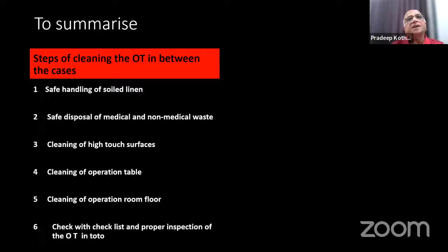The next talk was on instrument reprocessing. Cleaning, as I told you, is the most important step. It should be done as early as possible after the surgery to remove the debris as well as the blood clots. Second is inspection of the instruments for proper functioning, whether there is any debris remaining or not. If they are not functioning properly, you can lubricate them. If they are stiff, either they are not cleaned properly or you have to throw that instrument. Third is packing. There are many things available for packing, like trays and other materials. Fourth step is sterilization.